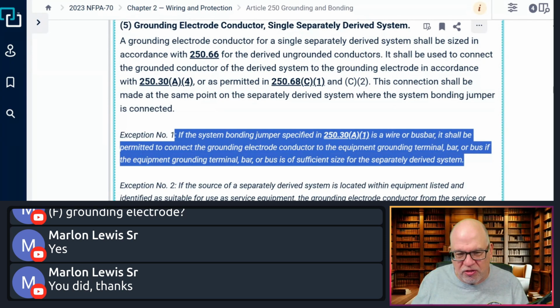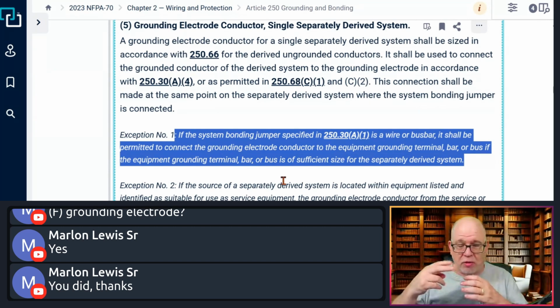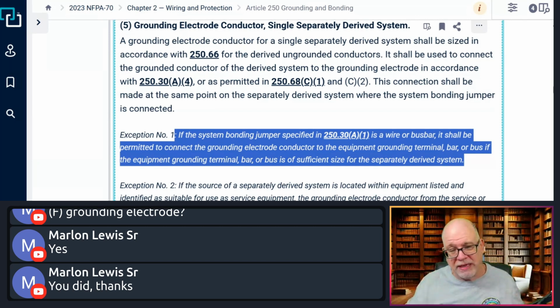If it's provided by the manufacturer, it'll have openings. Sufficient size also means the openings are properly sized for the conductor you're going to terminate onto it. That would come into question if you have all these knockouts and people add an extender lug. You do want to be careful, because if the manufacturer says the maximum size to be used on this bus bar is this size, that does not mean you can keep adding extended lugs or bigger lugs to receive a bigger wire than necessary. It does not always mean that on those small little bus bars. Just be careful, especially if you buy these accessory packs. Read the information. Many of them will let you buy an extender lug or an increased size lug, but don't just assume anything.